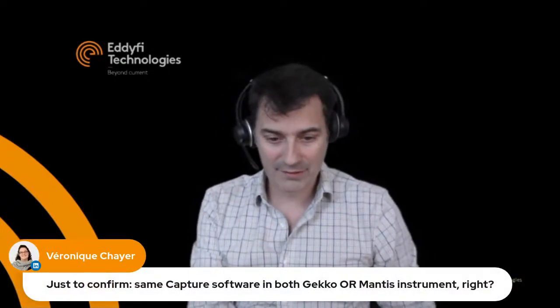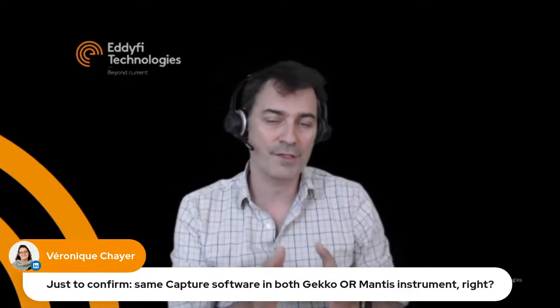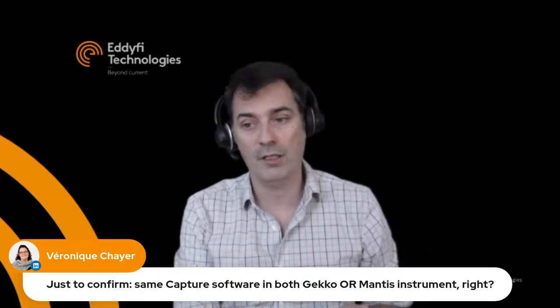That concludes the session. If you have more questions, my email is ffrd@edify.com — feel free to send emails or comment on LinkedIn or YouTube. And yes, Capture is the same software on both the Gekko and the Mantis, and also the PC version. The only difference between the Gekko and Mantis is the number of elements: the Mantis is a 16/64 element system. Thank you and see you next time.